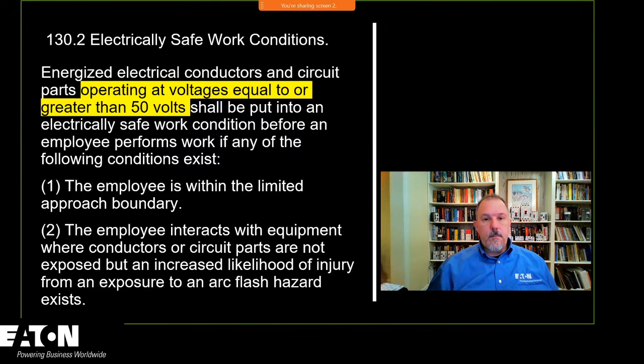And the language that Tom has on the screen is right up front in 130.2, in the front of Article 130. It tells us energized electrical conductors and circuit parts operating at voltages equal to or greater than 50 volts shall be put into an electrically safe working condition before an employee performs work if any of the following conditions exist. So that's the general rule. So if you're at 51, then this rule applies to you.